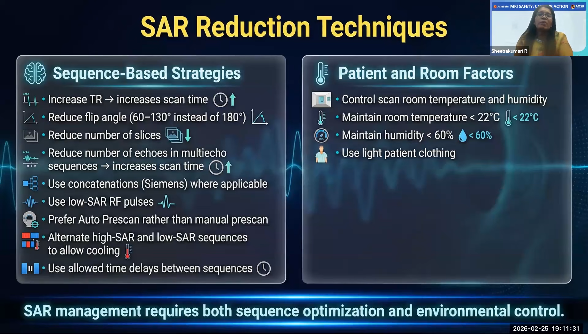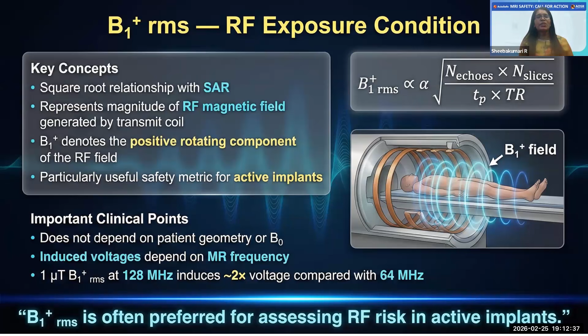The B1 plus RMS value is the most accurate method for assessing RF injury to a patient with implants, and it is calculated as the square root of SAR. The B1 value is not the amount of RF absorbed by the body. Instead, it is the magnitude of the RF generated by the transmit coil and transmitted to the patient. So it is a more accurate method for assessing the safety of an active implant. The unit is microtesla, and it is specified with the frequency, for example at 128 megahertz. A B1 plus RMS value of 1 microtesla at 128 megahertz induces double the voltage compared to 1 microtesla B1 plus RMS at 1.5 Tesla.